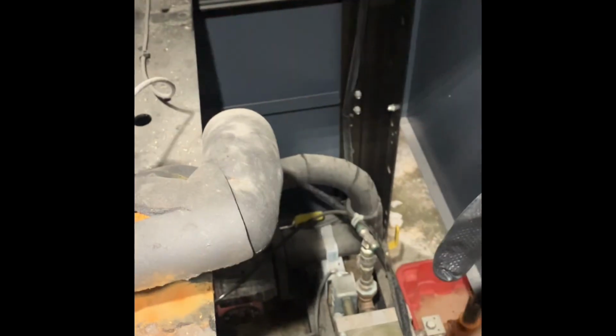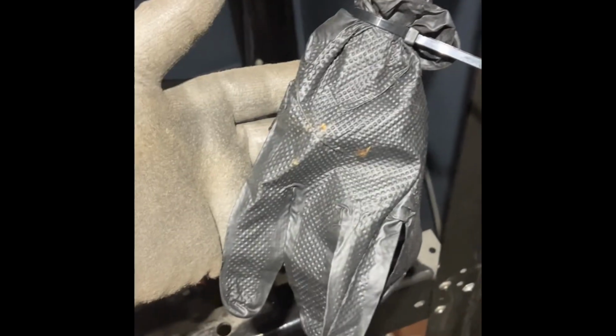And so what can happen on these is you could have an air to glycol heat exchanger leak, or you could have a refrigerant to glycol heat exchanger leak. And this guy right here will tell you either one. So like I said, right now I've got 11 psi suction pressure in my refrigeration system, but the air side of this dryer is still pressurized. And so we seal this glove over here, and if there were an air to glycol heat exchange leak, we should see that with the dryer off and air pushing back into the glycol system. The only place that really has to go is out the glycol vent loop and here. So this glove should be waving at me if we had an air system leak. It could technically push back to the refrigeration system, but highly unlikely.